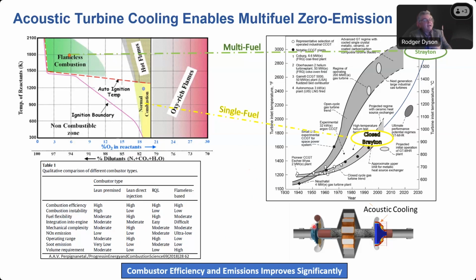So we can operate at these much higher temperatures. We now have the room we need, the boundary conditions we need, the flow conditions we need to operate in this flameless combustion regime. So it's inherently cleaner. Even if you use today's fuels with this system, in addition to being more efficient—we're about 70% versus say 30 to 40% for most internal combustion engines—more importantly, we're a lot cleaner when we're burning these fuels.